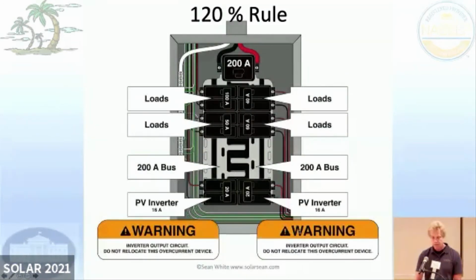And here it is too. One thing that was kind of confusing, I think it was worded wrong in the NEC, was they almost made it sound like it had to be one breaker. Let's do the math again. Let's say we have a 200 amp bus bar times 1.2 is 240. Subtract off 200 amps. We've got 40 left over.